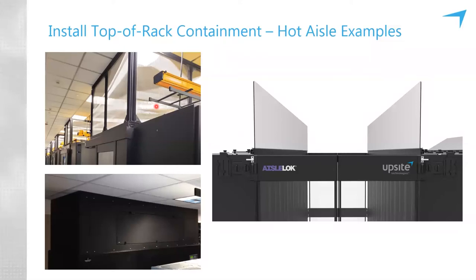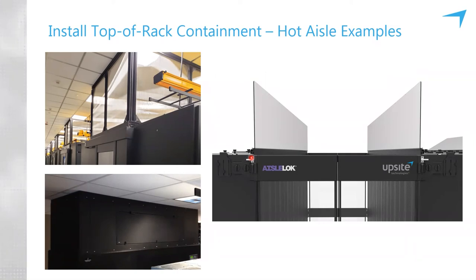That approach increases the delta T — you'll be returning much warmer air to the air conditioning unit, and when Lars discusses the science and delta Ts later, you'll understand why that's important. There are a lot of misconceptions in the industry about airflow science and cooling optimization, and that's a great example of how a creative solution can really improve efficiency.